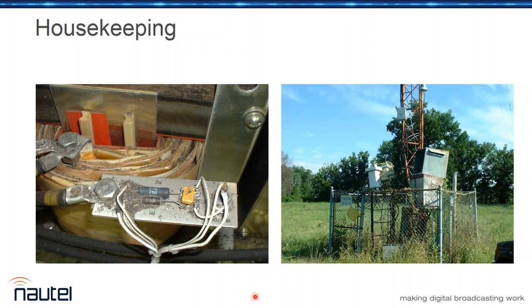So by all means, at least go in with a shop vac and clean it out. A lot of people like to use a brush and compressor. I prefer to vacuum, just because I like to know that the dirt's actually been removed from the transmitter and not relocated to a different place. But clean it out for sure.